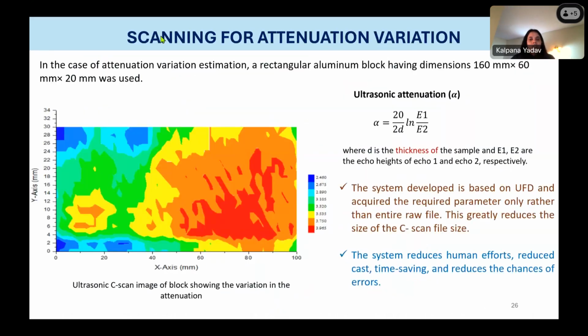So yeah, this shows when I did the ultrasonic attenuation measurement. You can see here easily how much attenuation there is in the block, the area you selected. The ultrasonic attenuation formula was already there in the program. I put that in, so it's going to pick echo 1 and echo 2, and it's just going to average this, and that can calculate ultrasonic attenuation easily in the samples.